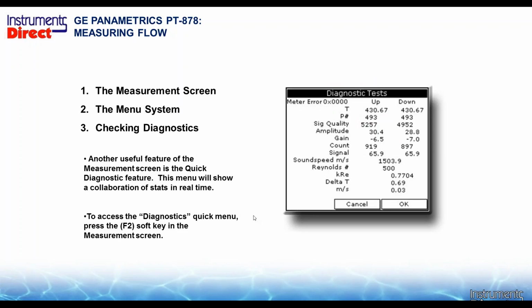If you get into trouble, one of the first things we'll ask you is, are you getting a signal? And you say, no, I'm not getting a signal. We may ask you to go to the Diagnostics screen, and you can get there by pressing the soft key across the top, the F2 button. It'll pop up Diagnostics. The first thing you look at there is, what is my upstream and what is my downstream transit time? If one of them is out, it tells you what the problem is, and that's usually the case.